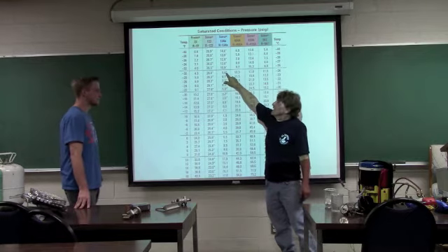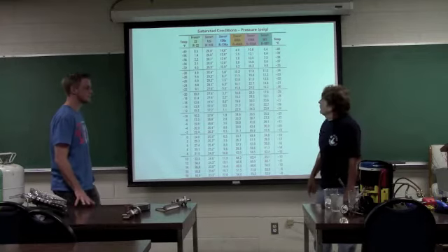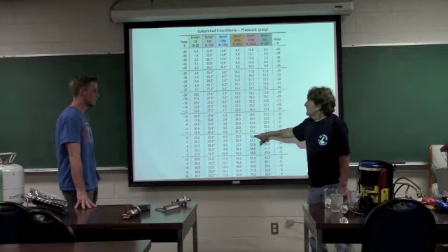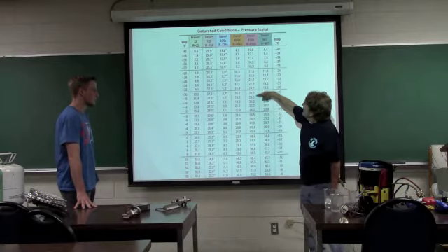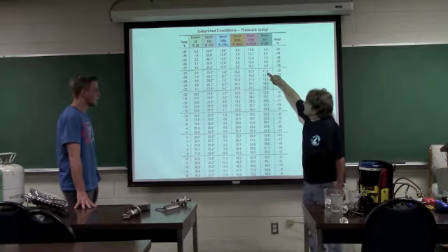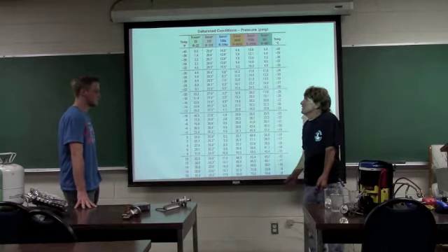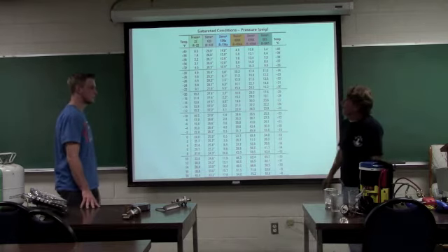Yeah, because these little marks indicate it's a vacuum, right? Correct. So this thing's actually running in a vacuum now. What if I had a requirement for 2 degree product, and I had a 30 degree delta T on the evaporator, and I was using 507? I'd be at 11.0 PSIG. Exactly. So there is a direct relationship here, okay?